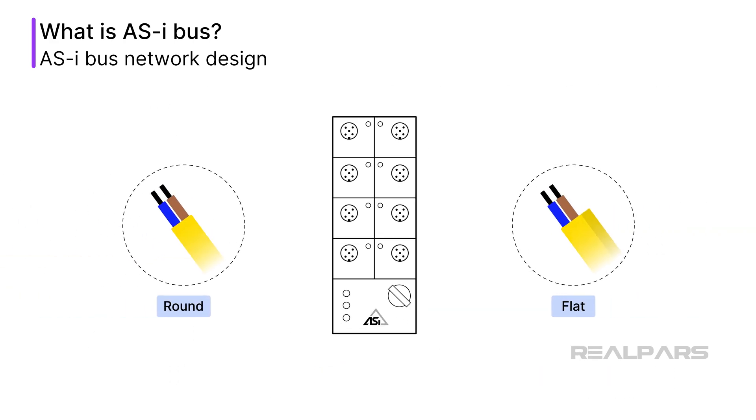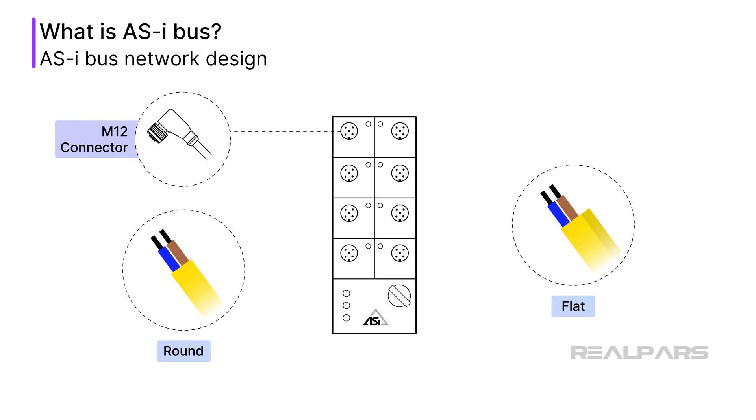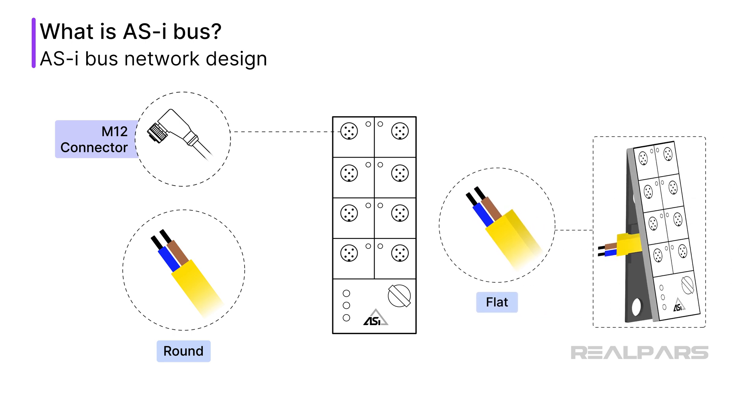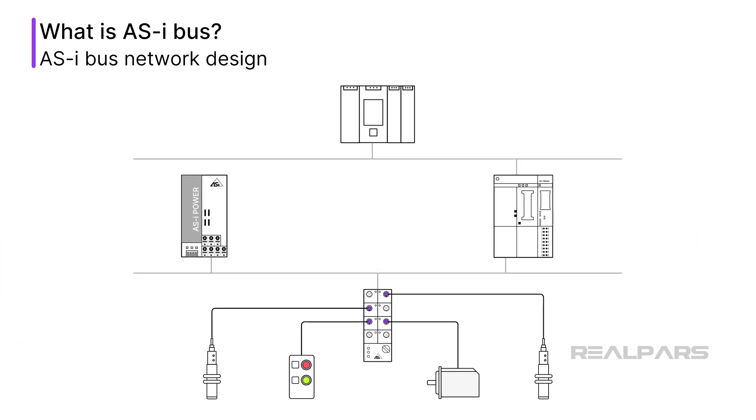AS-i bus cables come in a few varieties, including a standard round cable, which is connected by M12 quick disconnects or by terminating the two conductors. AS-i bus cables are typically yellow in color. Yellow flat cable is often used, and connections are made by simple vampire clamp connections. AS-i bus, unlike other instrument buses, requires no terminators at the end of the cable.